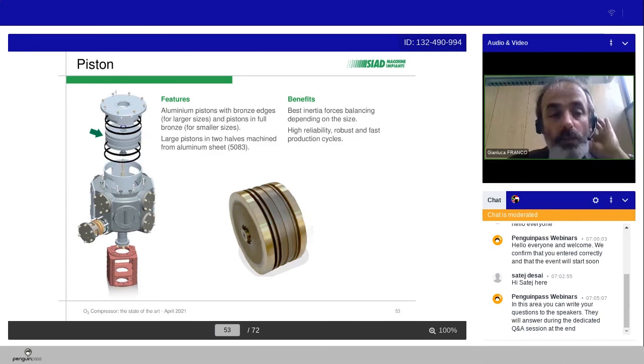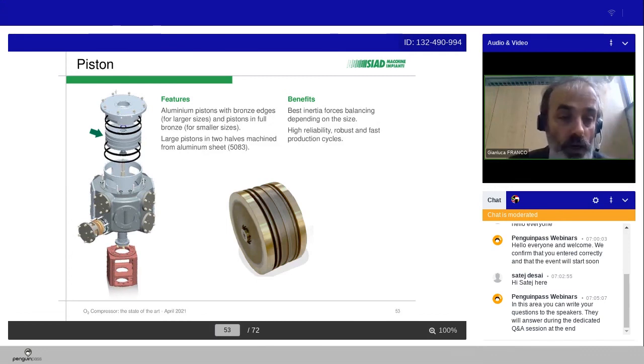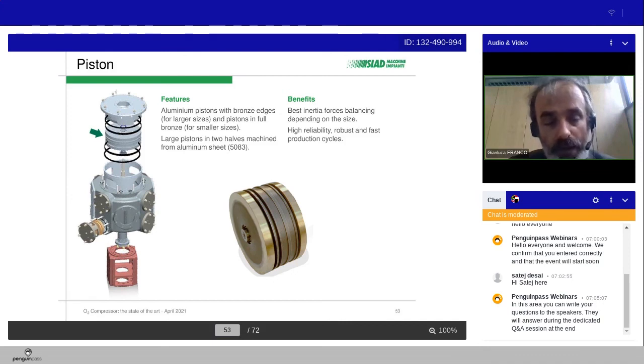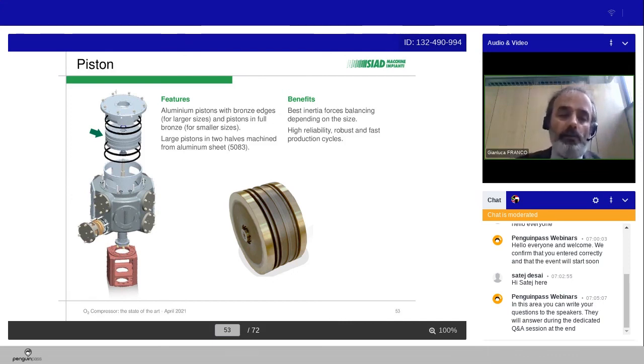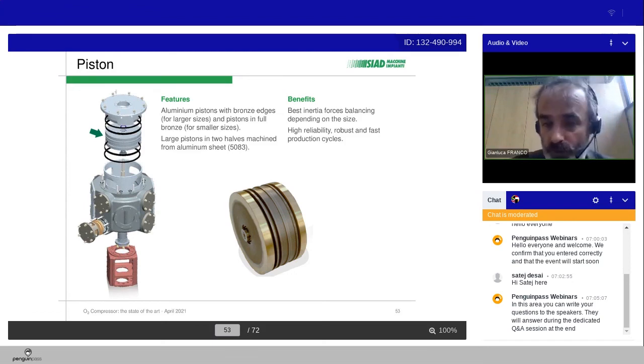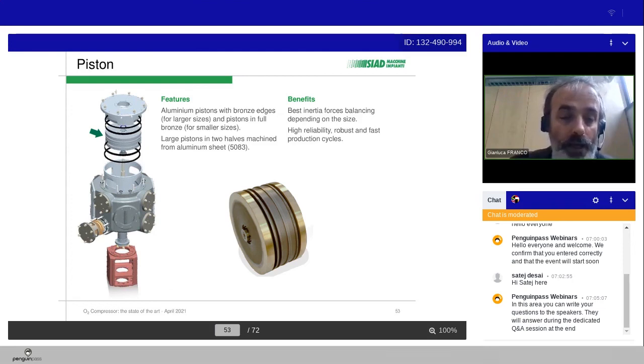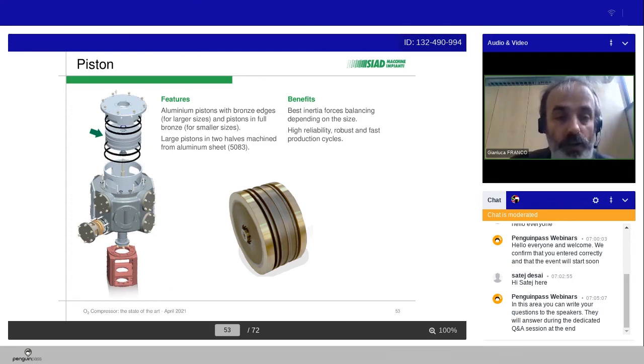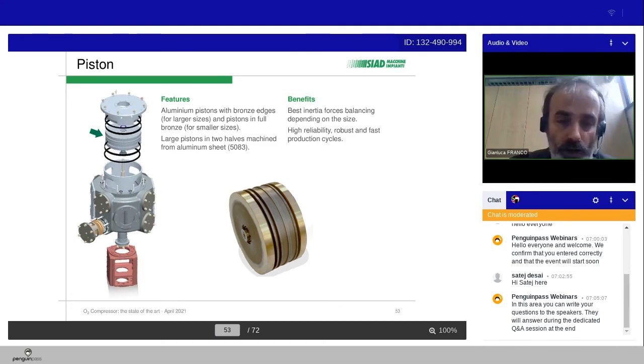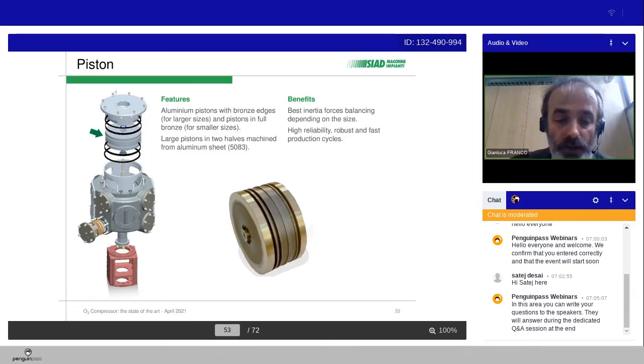About the piston, typically, aluminum pistons with bronze edge for large size or pistons in full bronze for small size. Of course, checking the unbalanced forces and couples generated due to the size of the compressor. In case of very high, big pistons, large pistons, we can rely on halves machined from aluminum sheets. In this case, best inertia forces balancing depending on the size.